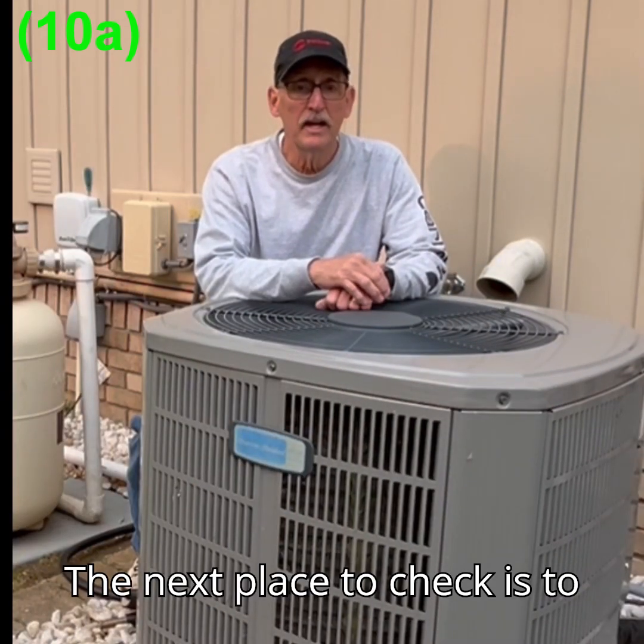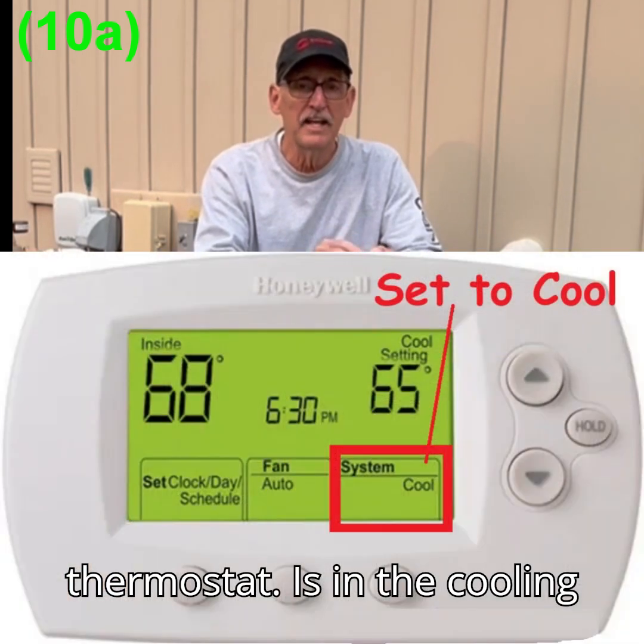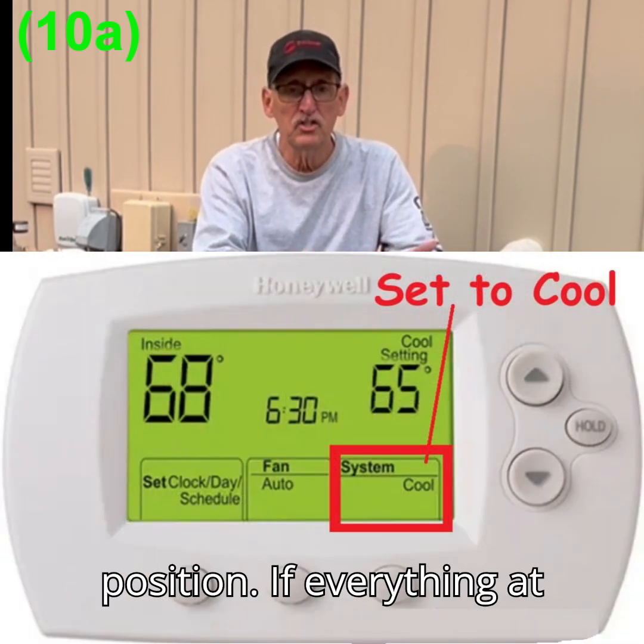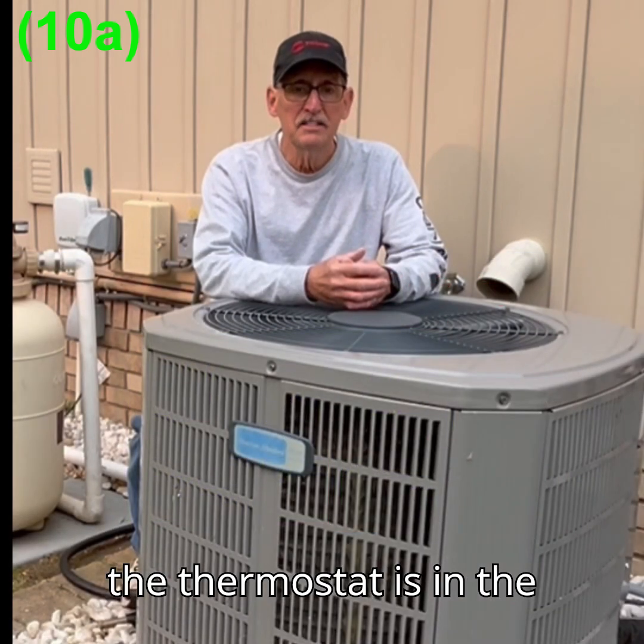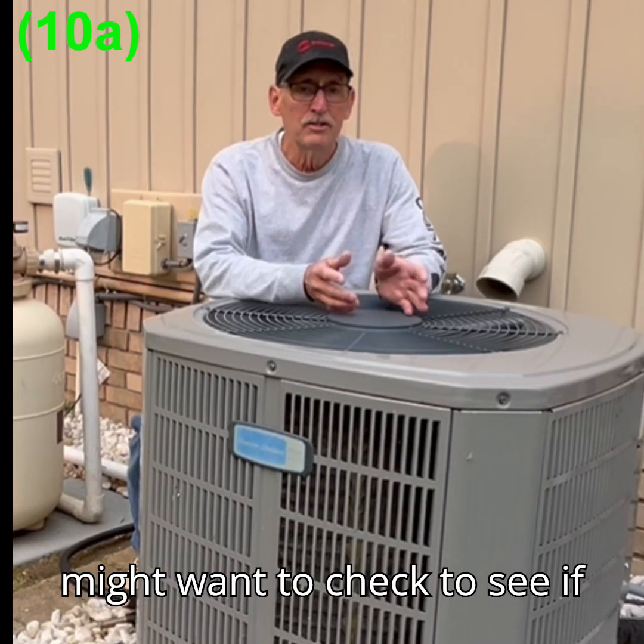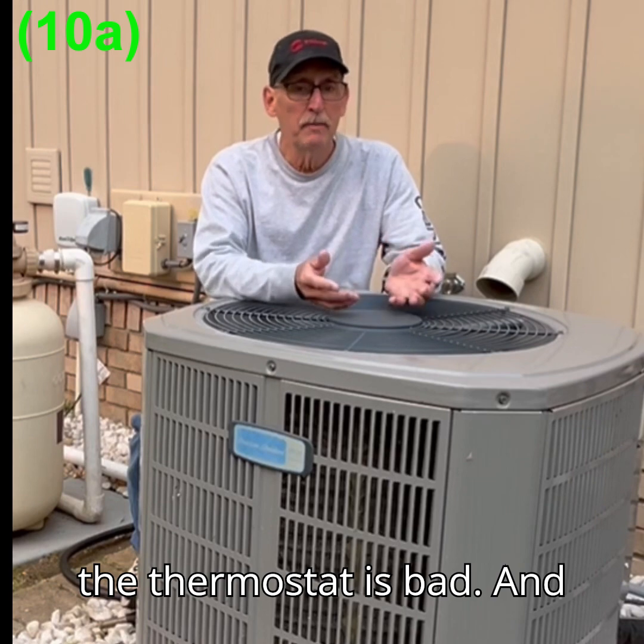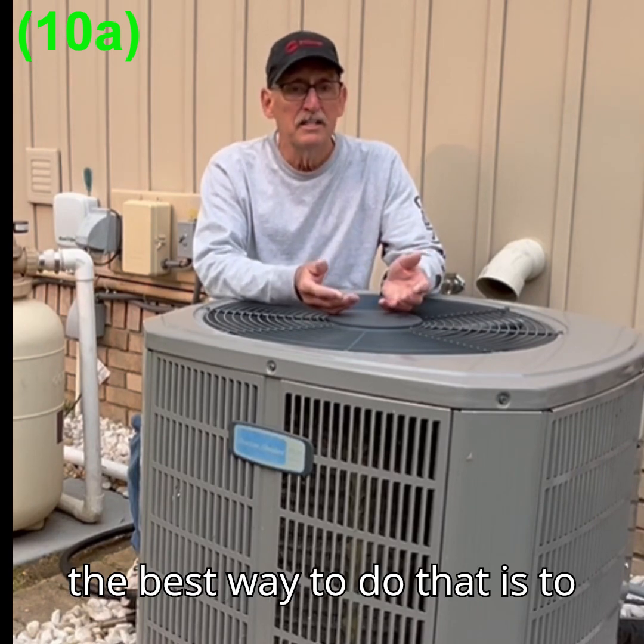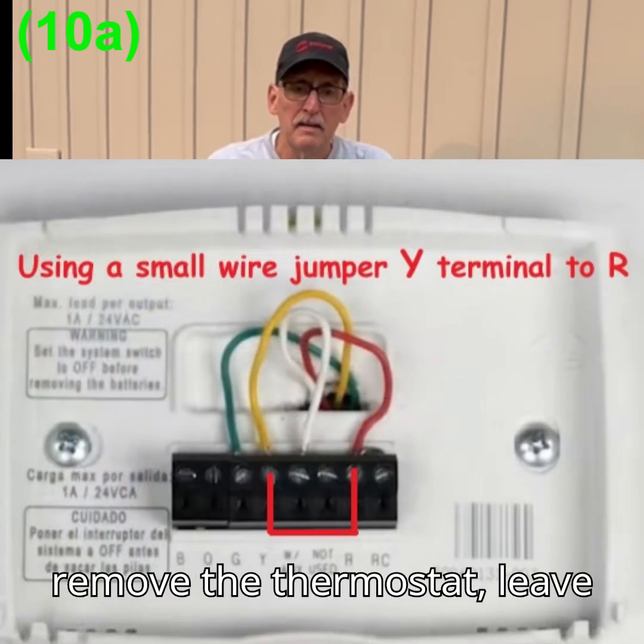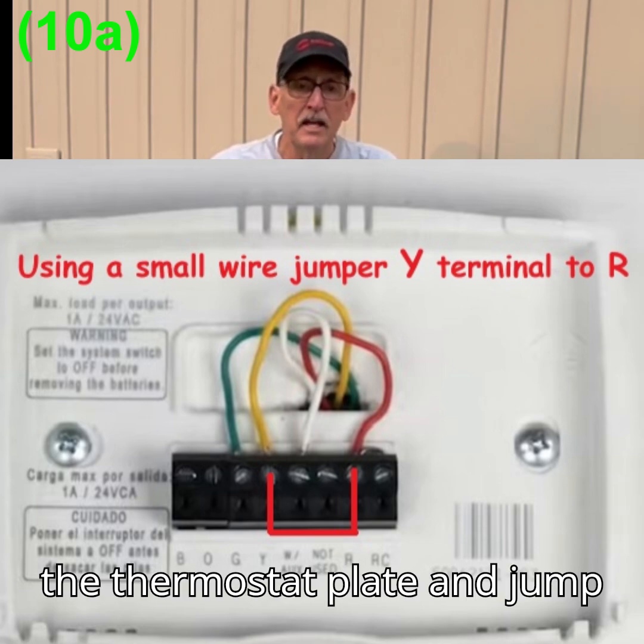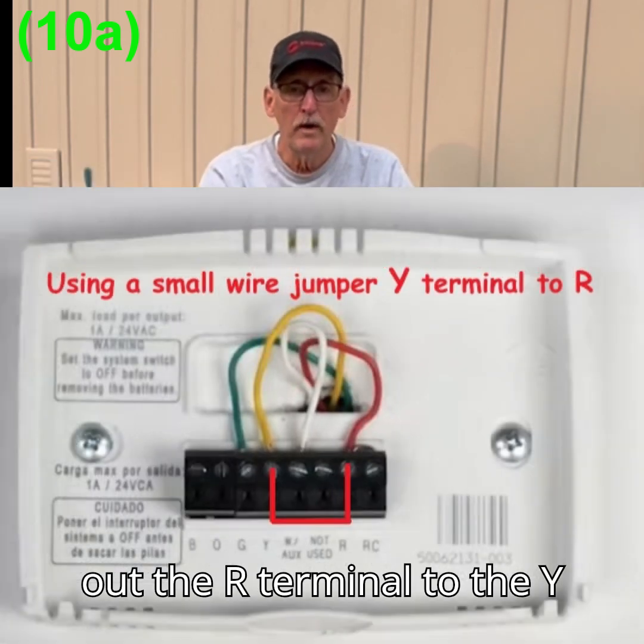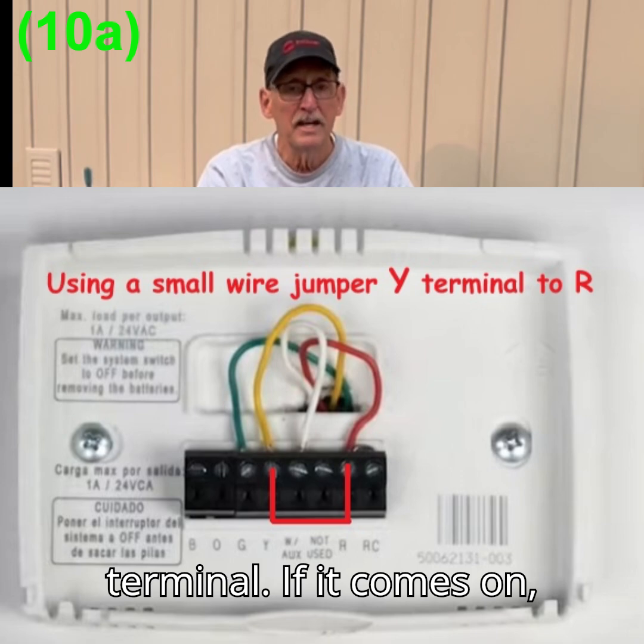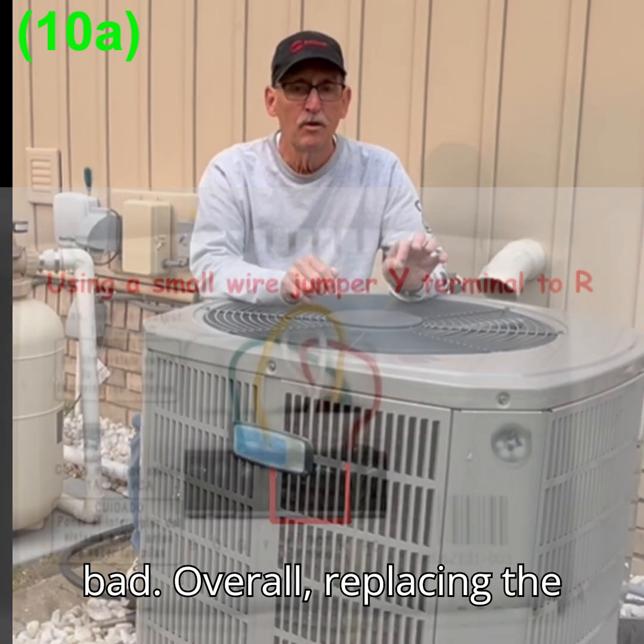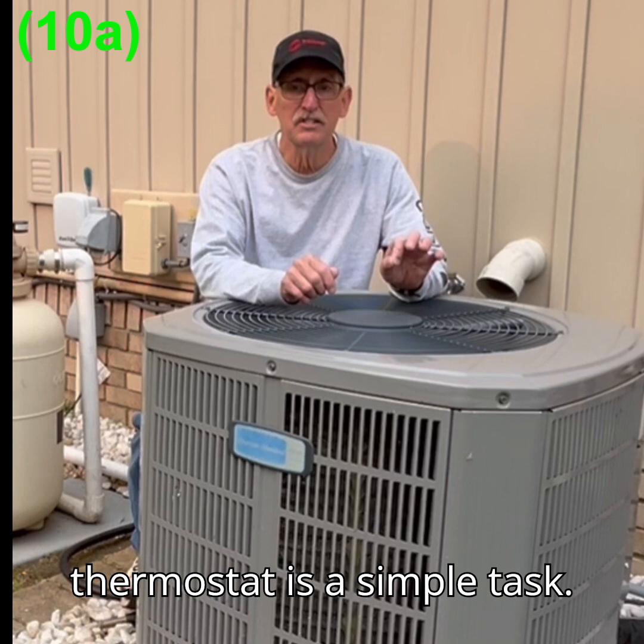The next place to check is to make sure that the thermostat is in the cooling position. If everything at the thermostat is in the right position, then you might want to check to see if the thermostat is bad, and the best way to do that is to remove the thermostat, but leave the thermostat plate and jump out the R terminal to the Y terminal. If it comes on, that means the thermostat is bad. Overall, replacing the thermostat is a simple task.